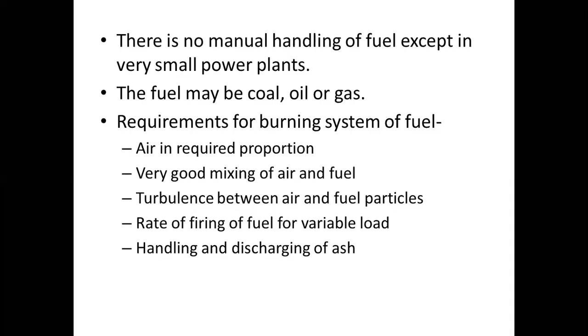If we discuss the basic requirements of a good combustion system, they are thorough mixing of fuel and air, you can say very good mixing of air and fuel, and the optimum air-fuel ratio required for complete combustion, maintained over our full load range. Our combustion equipment must have accurate and fast response to load demand, continuous and reliable ignition of the fuel, practically distillation of volatile components of the coal, and very good control over the point of formation, holding, accumulation and discharging of the solid residue of the fuel, that is known as ash component in the fuel.